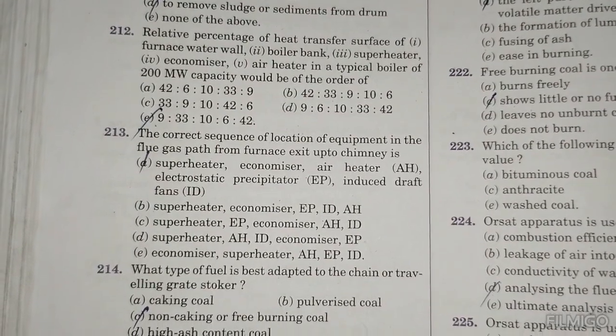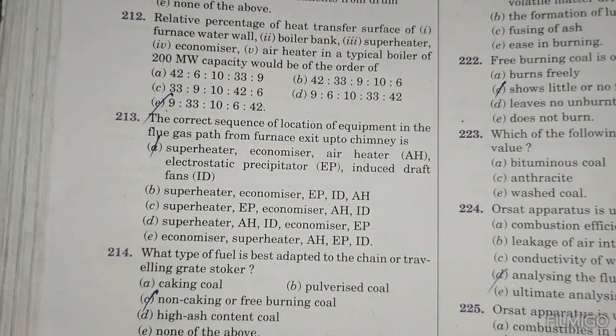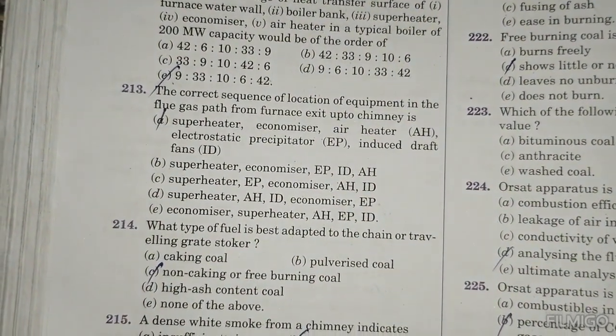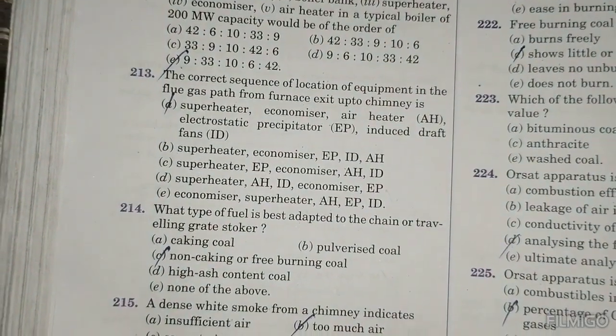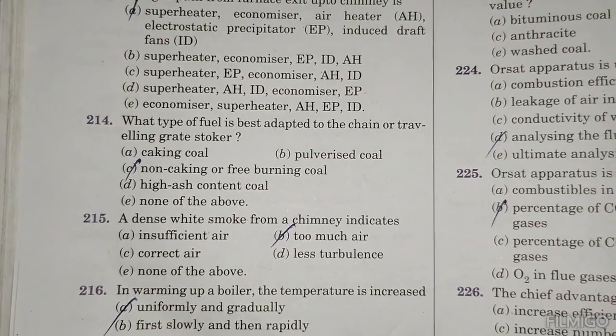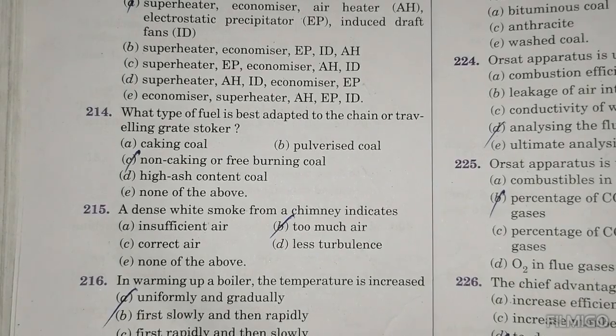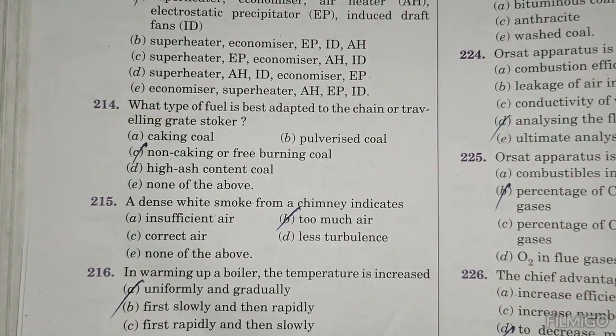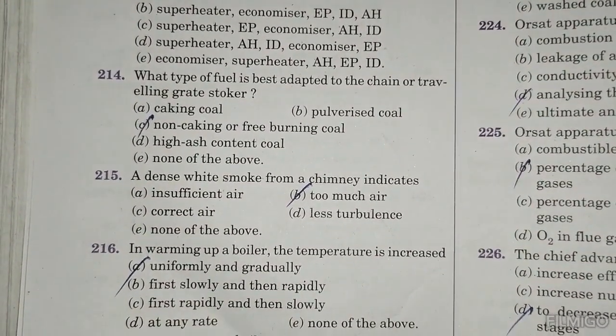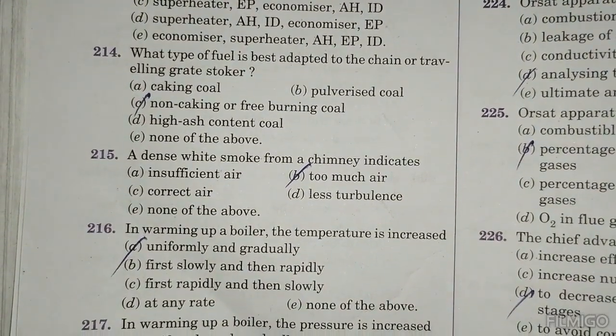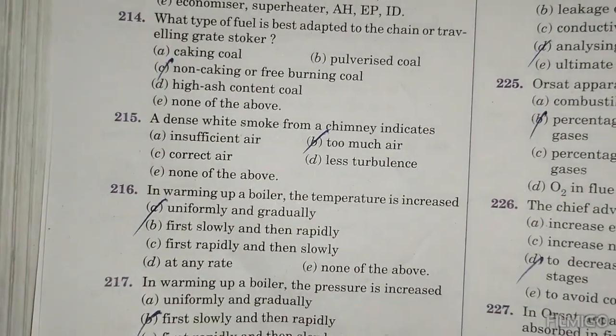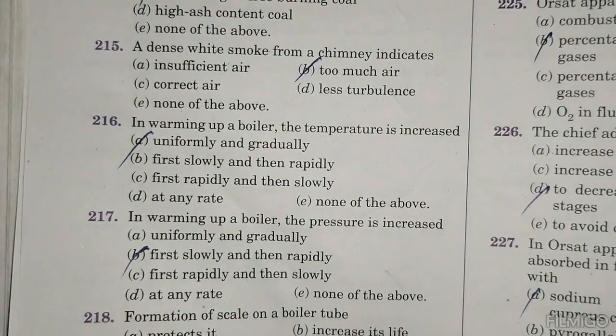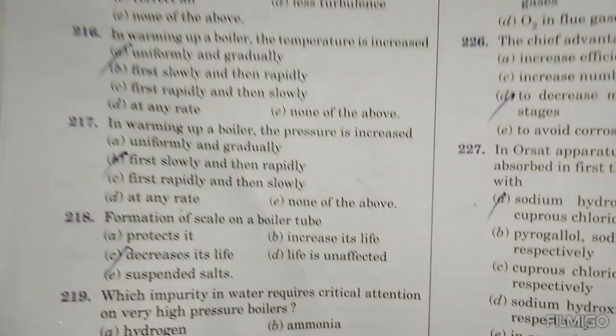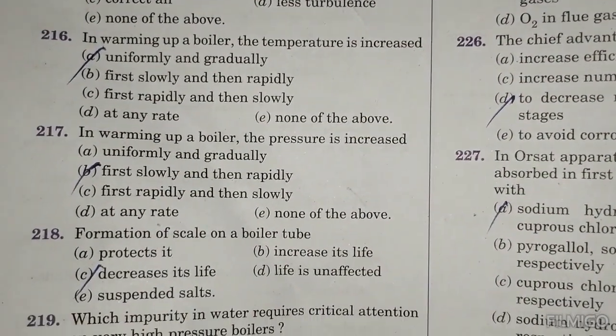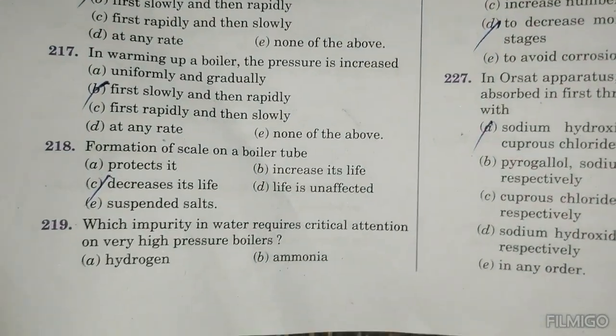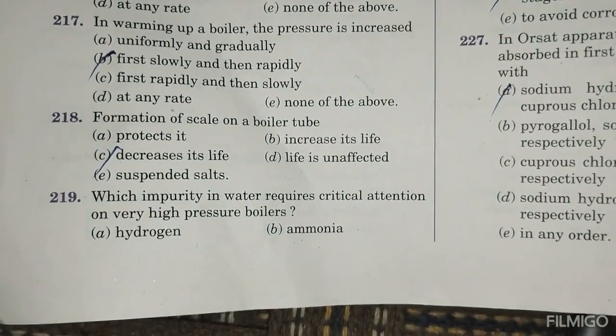The correct sequence of equipment location for the flue gas path from the furnace exit up to the chimney is superheater, economizer, air heater, precipitator, induced draft fans. What type of fuel is best adapted to the chain and traveling grate stoker? Non-caking, free burning coal. A dense white smoke from a chimney indicates too much air. In warming up a boiler, its temperature increases uniformly and gradually. In a warming up boiler, the pressure increases first slowly and then rapidly. Formation of scale in the boiler tube decreases its life.